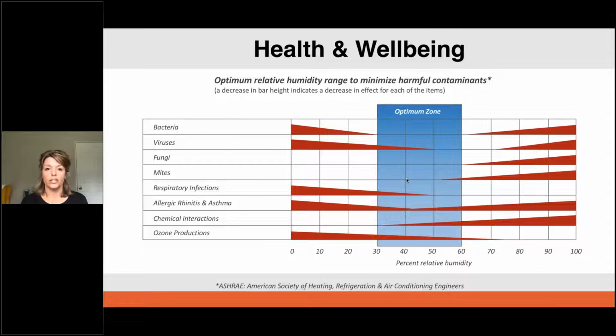Here's the ASHRAE chart for health and well-being, showing the optimum zone of 30 to 60%. You can see that 50% is really ideal for controlling bacteria, viruses, fungi, mites, and respiratory infections. So if that can be our goal for where we're reading the humidity—since we'll have a sensor somewhere trying to control relative humidity to 50%—if we can achieve that in that space, then areas farther from the sensor might go up a little, but at least we can keep it below 60% for sure.